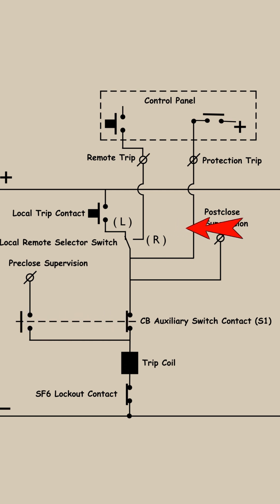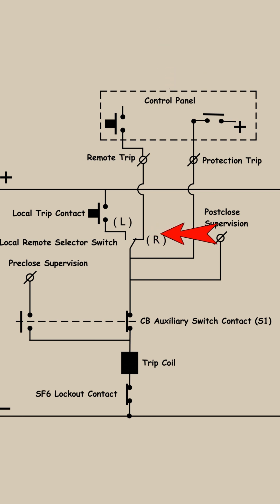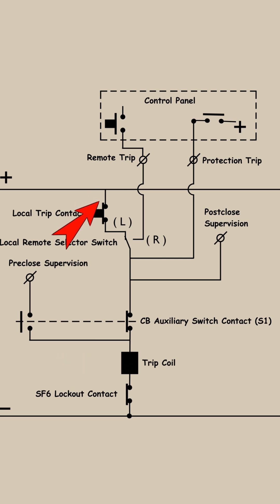This is the local/remote switch. Currently, the switch is set to remote, so you can operate the circuit breaker from the control room. If it is set to the local side, then by pressing this push button or rotating the associated tripping switch, the DC voltage — meaning local DC voltage — will come to the tripping coil following this path.